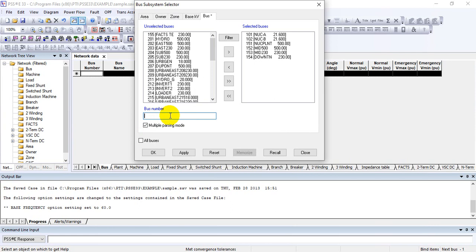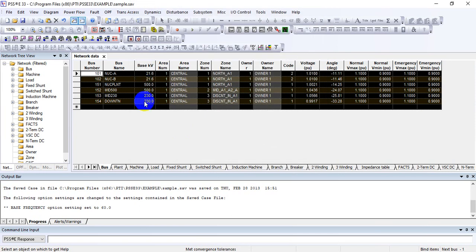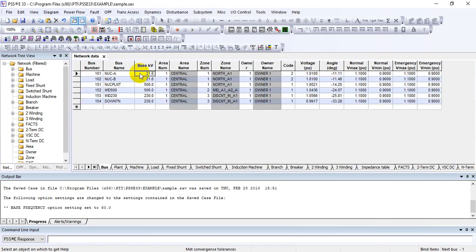To load all buses at once, after entering each bus number with a comma, select the 'Multi Parsing Mode' checkbox and then click anywhere. You can see that all buses are selected. This is useful when making a subsystem for a wind generation area or any specific area — just get the bus numbers in Notepad, paste them in the bus number row with commas, check Multi Parsing Mode, and click Apply.